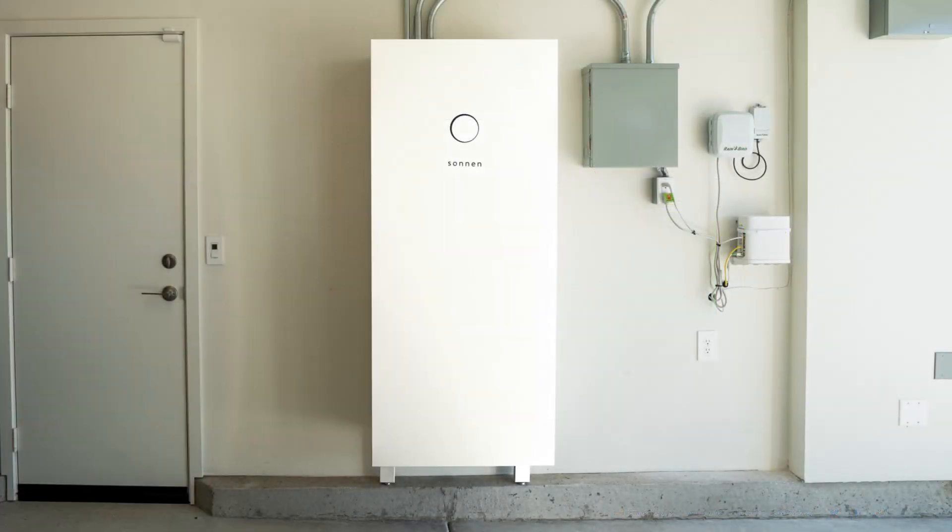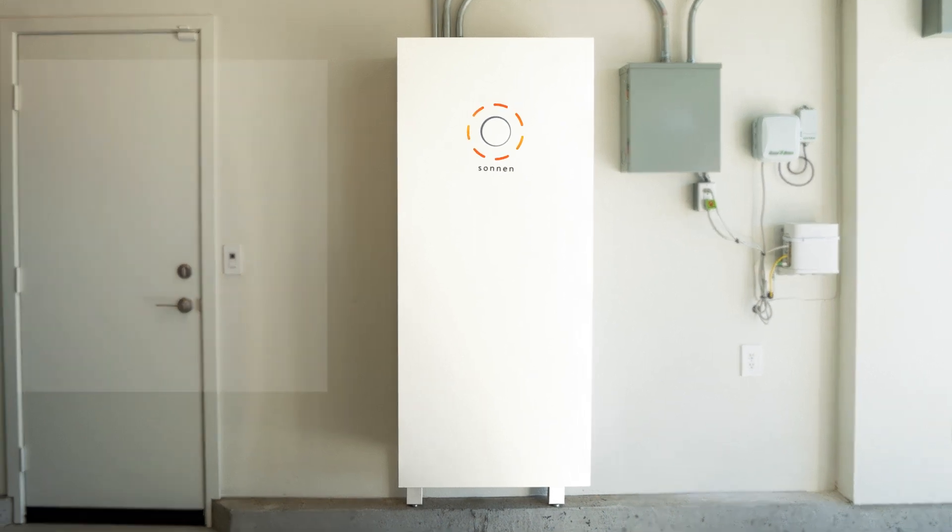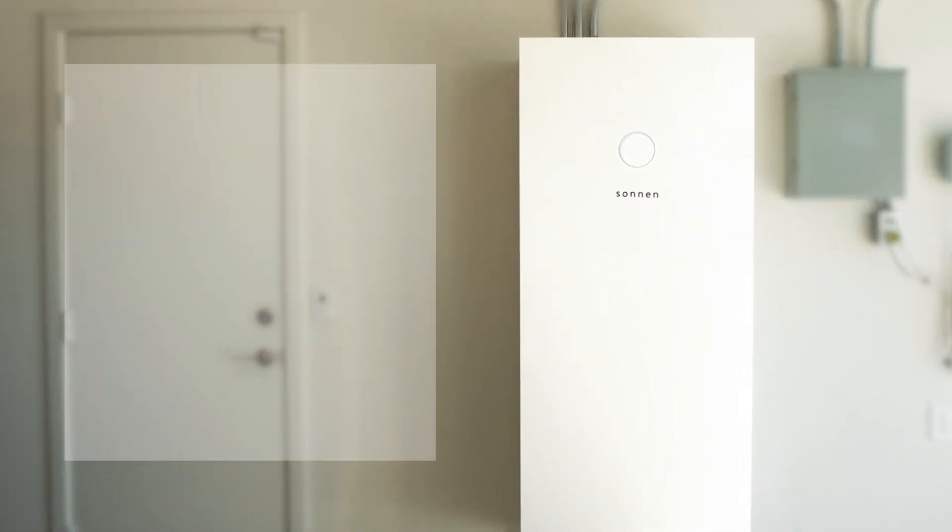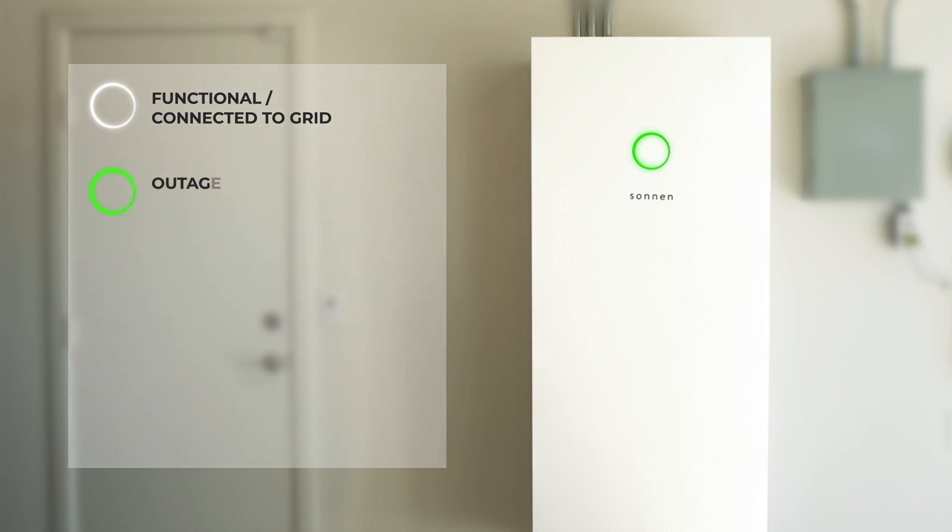Now, let's take a step outside of the portal to the battery itself. The Sonnen Halo is an excellent resource for troubleshooting. If your battery is functioning perfectly and connected to the grid, it will pulse white. During an outage, the halo will pulse green. This means it is in off-grid mode and providing energy to your backed-up loads.